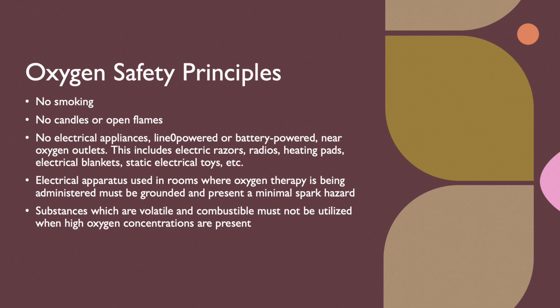Patients love to bring in their own electrical devices, and those devices are notorious for causing something called 60 hertz artifact, especially heated blankets. And it's going to be 60 hertz artifact because when they plug in their device, in the United States, we have AC, which operates on 60 hertz. So that's the kind of interference you'll see. Heated blankets are not grounded, and they pose a significant fire risk.